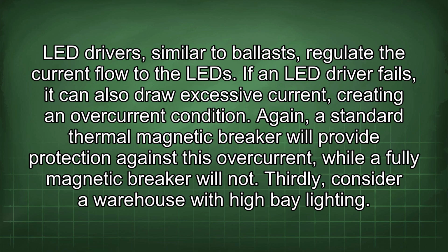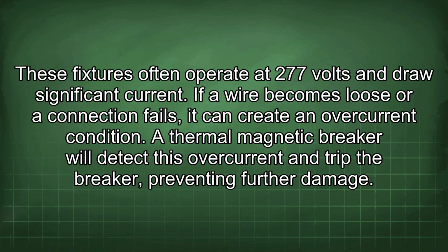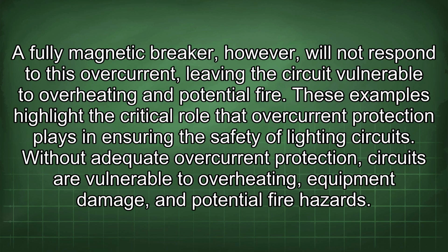Thirdly, consider a warehouse with high bay lighting. These fixtures often operate at 277 volts and draw significant current. If a wire becomes loose or a connection fails, it can create an overcurrent condition. A thermal magnetic breaker will detect this overcurrent and trip the breaker, preventing further damage. A fully magnetic breaker, however, will not respond to this overcurrent, leaving the circuit vulnerable to overheating and potential fire.